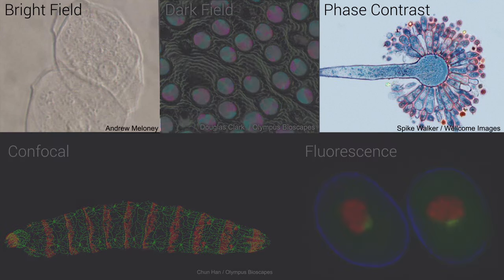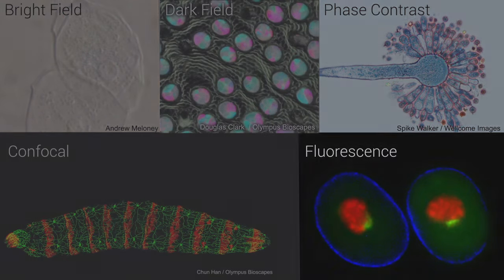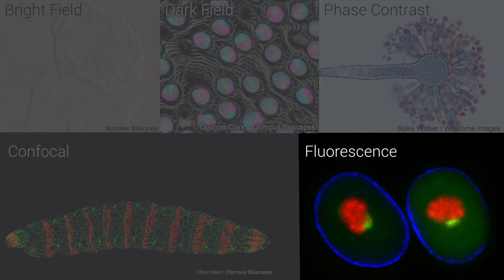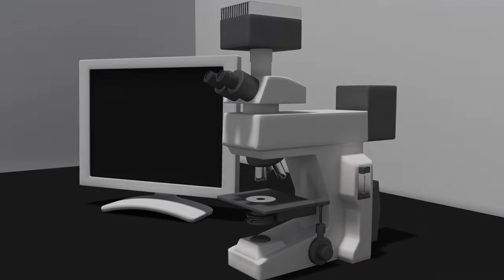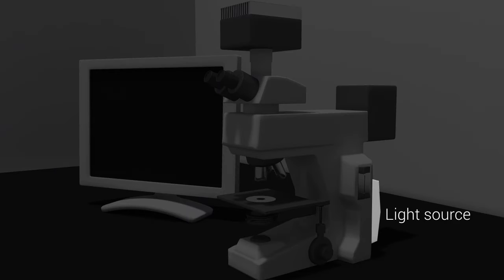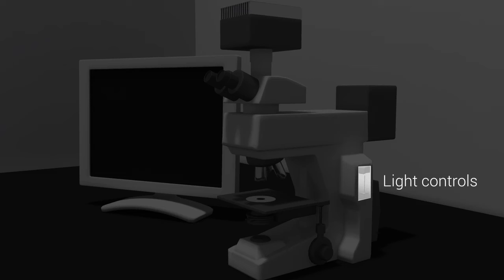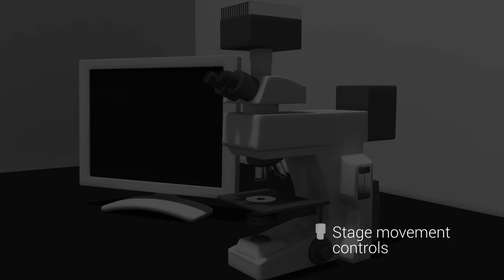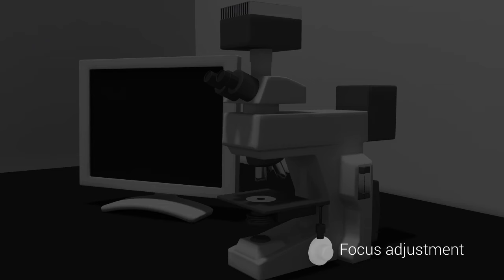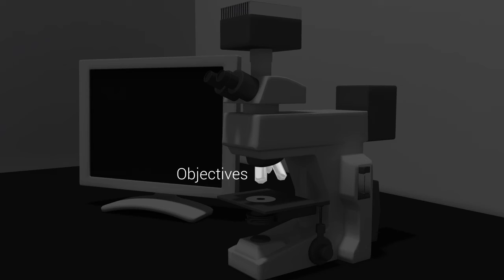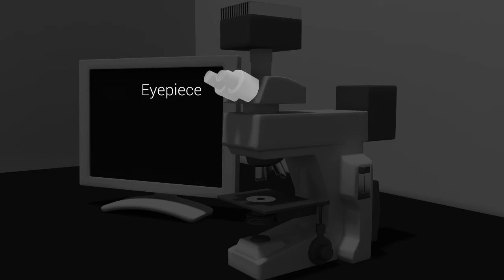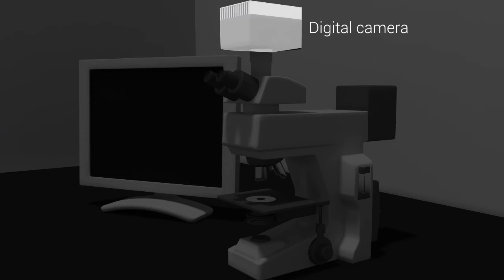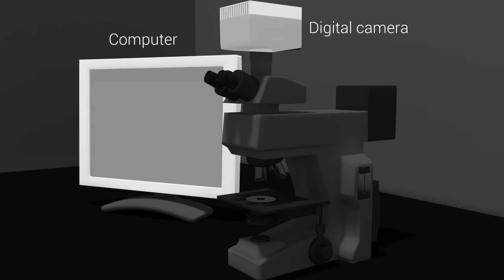We will touch upon bright field and phase contrast microscopy, and then discuss fluorescence microscopy in the next animation. All light microscopes have several components, including a light source such as a halogen light bulb or laser, a light source on-off switch with a knob to adjust its intensity, a diaphragm and condenser to focus the light onto the sample, a stage to hold the sample, controls to move the stage, focus knobs for coarse and fine focus adjustment, objectives to magnify the sample, and an eyepiece through which the researcher can view the sample. In addition, microscopes are often fitted with a digital camera and a computer for a scientist to capture images viewed through the microscope.